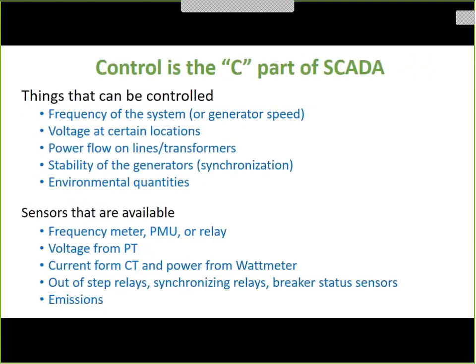Okay, let me just keep going here for a minute to get to the control part. There's lots of things that we call control. Most of them don't have H-infinity or even PI control, let alone PID control. The controls for the grid are sometimes discrete. You have a circuit breaker that opens up or it doesn't open up, and the thing that decides that is the relay. The relay decides when to open up a circuit breaker. We look at things for voltage. We want the voltage to be good, so that's clear. We want the frequency to be good, that's easy. We want the power flow on the lines to be less than the ratings, and we want the generators to all be stable. And there's environmental stuff.